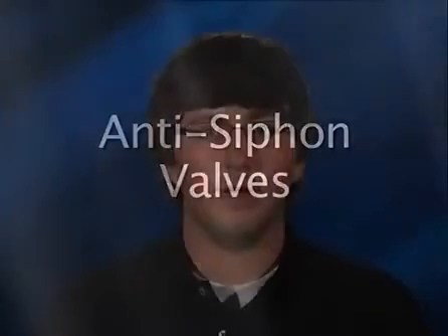Above-ground tanks typically have a mechanical type level gauge for direct reading of tank levels as a backup to electronic gauging systems. Above-ground tanks are commonly located such that fluid level in the tank is above the point of use. Therefore, inadvertent fuel could be siphoned from that tank. To prevent siphon flow, an anti-siphon valve is typically located at the top of the tank. The valves are either fully mechanical or an electric-operated solenoid valve can be used. The fully mechanical valves are usually configured as a normally closed valve with an adjustable spring resistance to equal the siphon head. Then a positive suction from the transfer pump allows the valve to open and flow.